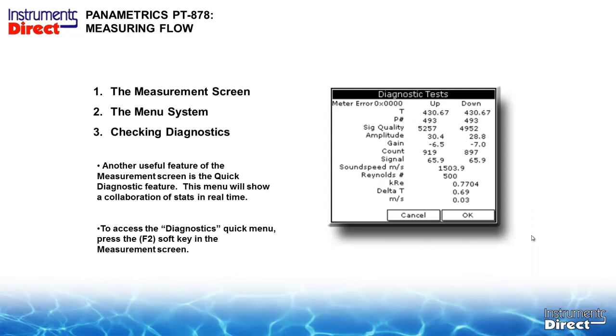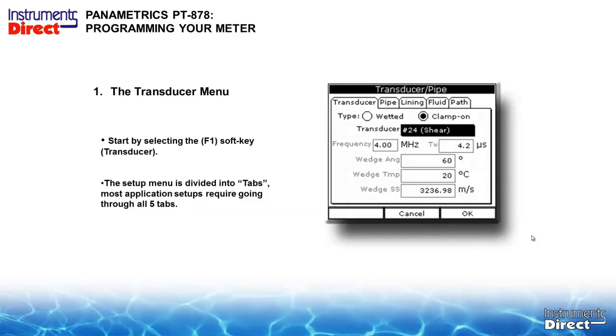Now, another useful feature of the measurement screen is the quick diagnostic feature. Basically, if the meter reads and gets your flow, you're done. You're never going to use the diagnostics. If you have an application that's not working, that's when you call support. That's when we'll say, let's take a look at your diagnostics. The most important thing you're going to look at in the diagnostics would be the signal strength for the upstream and the downstream. That's another place to look if you have an exotic liquid. So that's the first place to go should you have a problem in monitoring your flow. To access the diagnostic quick menu, press F2, the soft key, in the measurement screen.